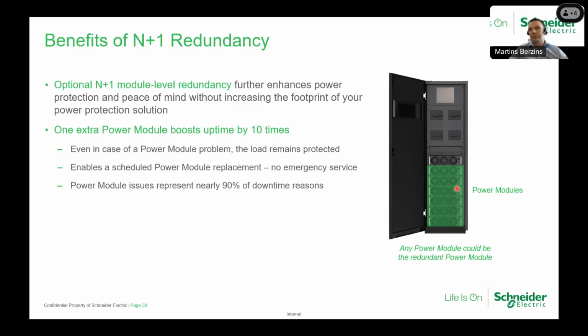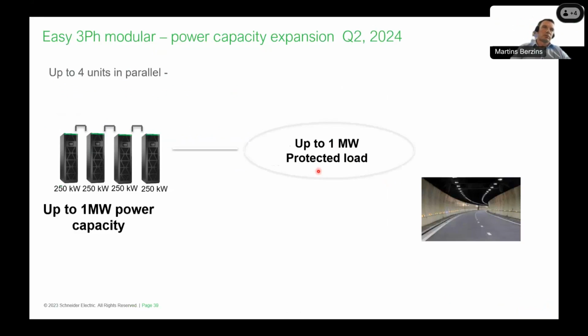This also means that, for example, if you have one spare power module inside the UPS and one of the modules fails, it's not an emergency state or emergency replacement. You can schedule a safe replacement without the urgency or emergency situation, and of course the load remains protected. Regarding the paralleling, in Q2 2024 we'll have an updated firmware, and then we will be able to connect 4 modular 250 units in parallel, reaching up to 1 megawatt of protected load.